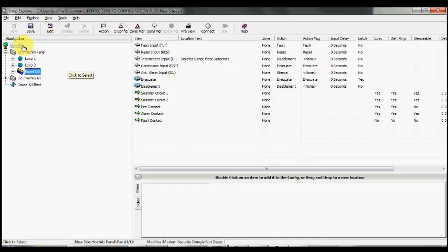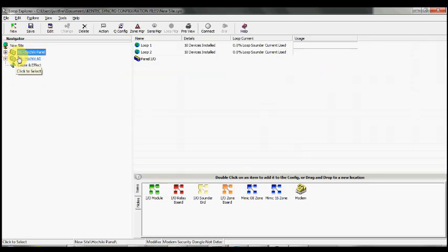So effectively each of the Syncro panels have the facility to be placed into a one-man test mode, whereby the sounders, when a detector is operated, will sound for approximately 5 seconds and be recorded in the event log, and then effectively will silence, and then when the next device is tested again it will resound.